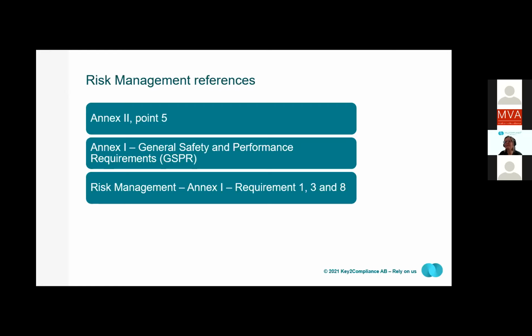In practice, you would need to describe or state the method that you choose for compliance with these requirements, for example, the standard 14971. And then you would also need to list the evidence for compliance with that chosen method or standard. A question that is asked quite often, and might probably not be new to those of you that have been around for a while, is if a notified body would look at the compliance with a standard and why they do that, since standards are voluntary to use. And the answer is that you could use any method of your choice to fulfill the GSPRs. However, it needs to be at least in line with the state-of-the-art method. And for risk management, this is 14971. And if you have said that you would comply fully to that standard in your GSPR checklist, you will probably also be evaluated for compliance with that standard during the technical documentation assessment from your notified body.